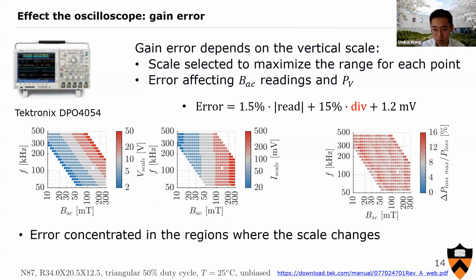But if we want to find this error, we can look at the manufacturer's data sheet. Finding this error is actually quite challenging, in the sense that the oscilloscope manufacturer only provides a maximum error, as shown in the error analysis here. Regarding the overall error, both the probes will obviously introduce some error in the measurement, but the oscilloscope also contributes significantly to the error. As you can see, besides the 1.5% of error just from the reading, and a fixed error of about 1.2 millivolts introduced to your overall system, there is a really crucial 15% maximum error that can be introduced from the vertical scale.